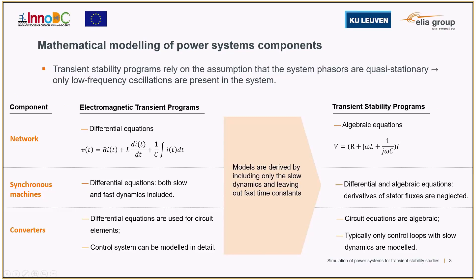The network equations are transformed from differential equations in EMTP to algebraic equations based on steady-state phasor equations. For synchronous machines, only the slow dynamics is included and the derivatives of the stator fluxes are neglected in the simplified model. For converters, some simplifications are made in the circuit equations, which become algebraic, and in the control modeling — only the control loops with slow dynamics tend to be included.